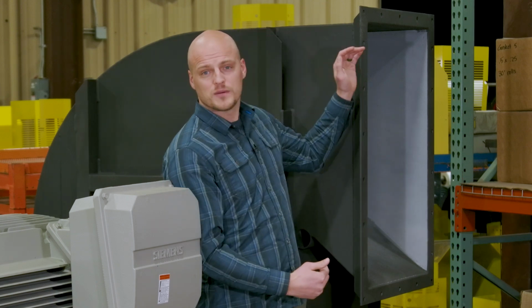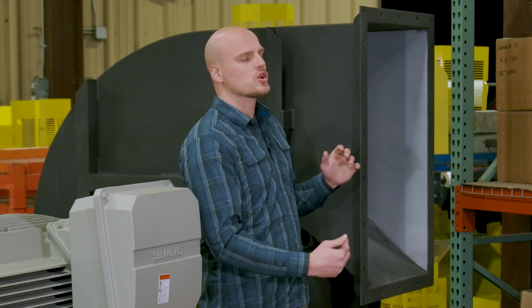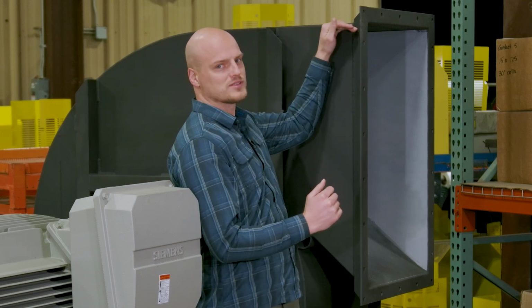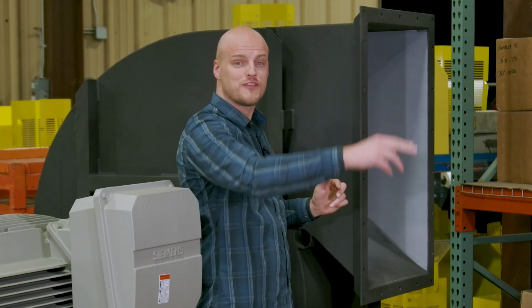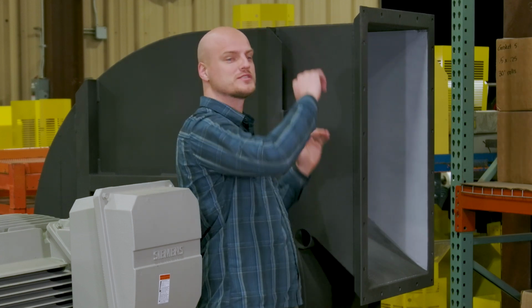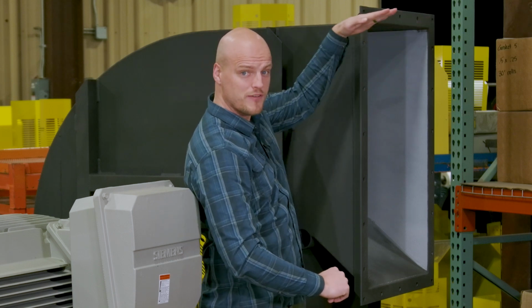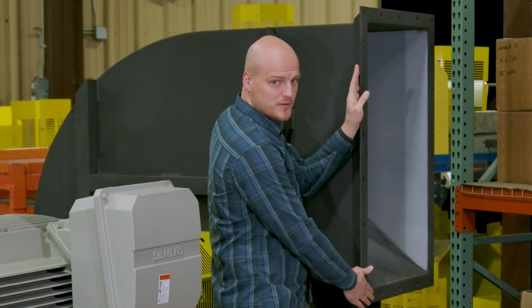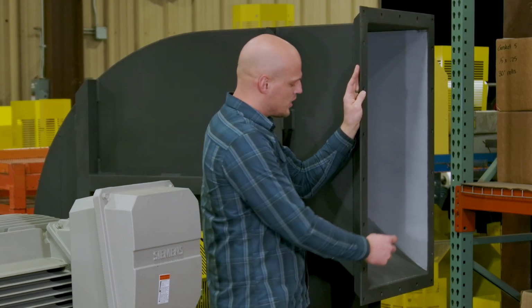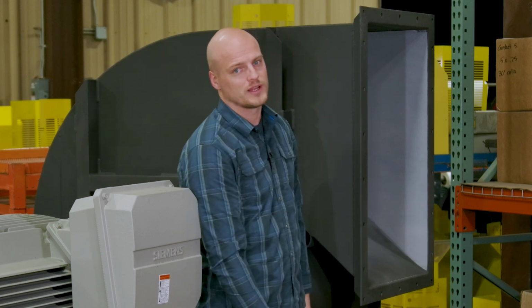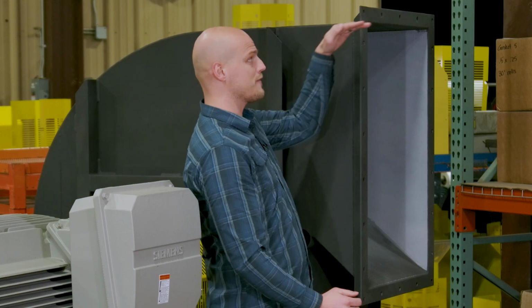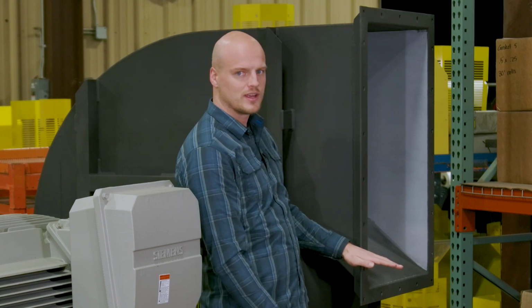So as air comes off the outlet of the fan, you're going to have your highest velocity profile at the very outside of the housing because air has come really fast around the volute and out here. So it's very fast here, but down at the very bottom of the outlet, in this example, your air is still curling and it can curl back into the outlet. So your profile is very fast here, very slow down here.